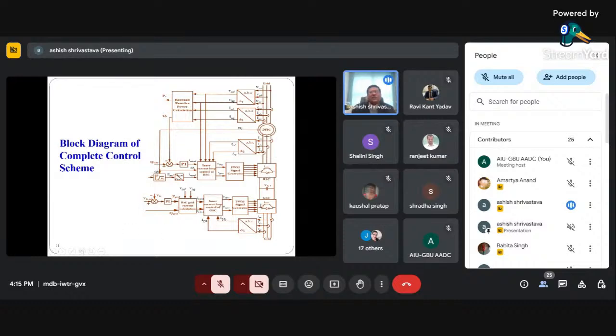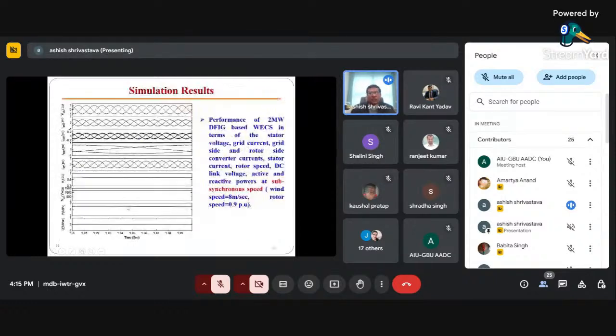Similarly, for the GSC side, there is an inner current loop. The actual current has to be sensed and converted into DQ, and the actual voltage is sensed, compared with the reference voltage, and passed through the PI controller. Then reference current generation with the actual voltage sensing, and then the inner current loop has to generate the pulses for your PWM signal generator. So this is how the actual implementation can be done for the complete control scheme.